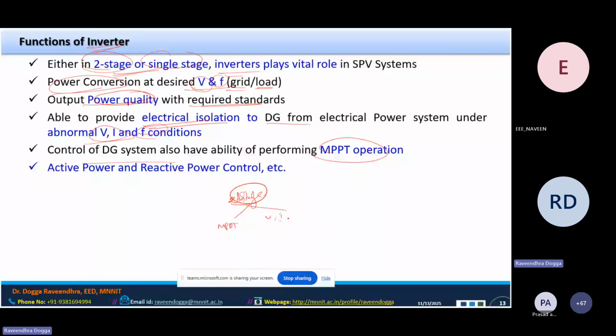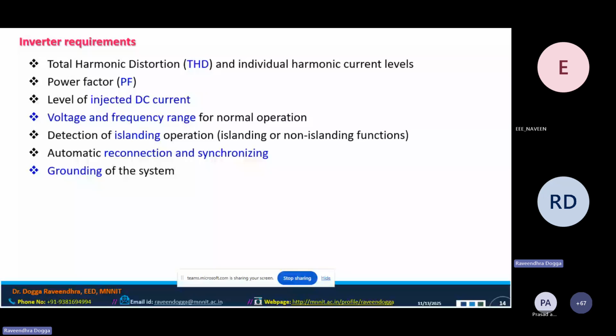You need to have proper active and reactive power control, and also take care of THD and individual harmonic current levels, power factor requirements, and offset DC current injection, which some power conditioning units inject. There are limitations and regulations on that too, like the special VDE standards from Germany, which strictly govern DC offset currents. There are also requirements for voltage and frequency range for normal operation, detecting islanding, automatic reconnection and resynchronizing, and proper grounding. Some topologies do not allow the PV as well as the load to be grounded. We'll see that.